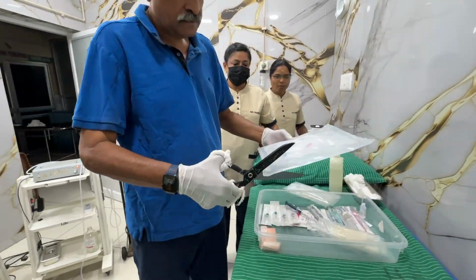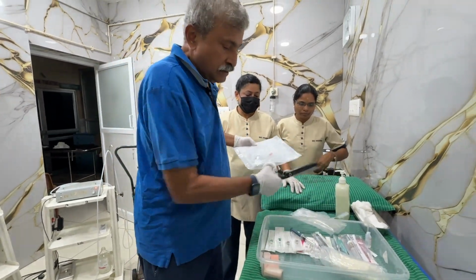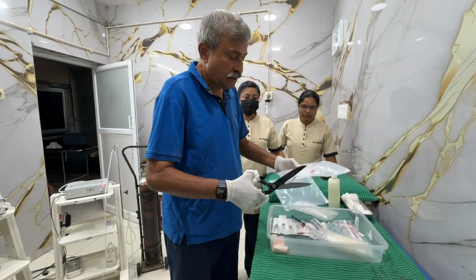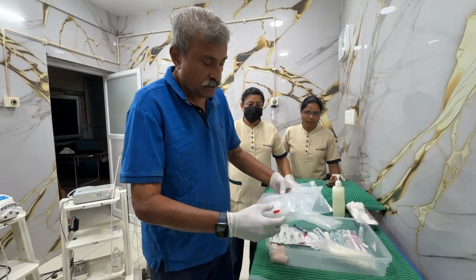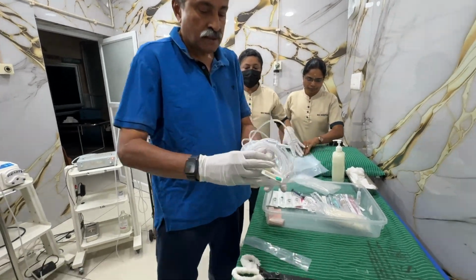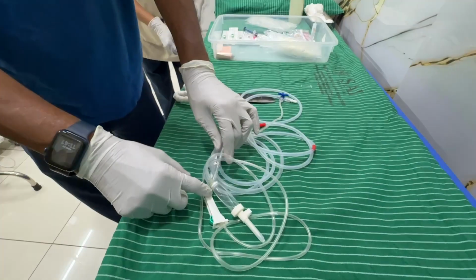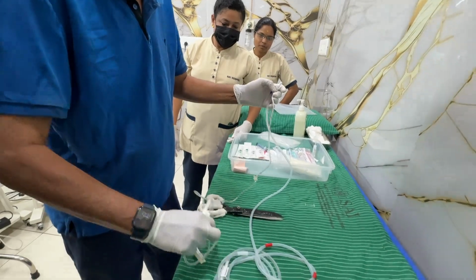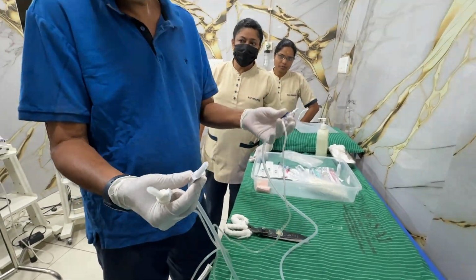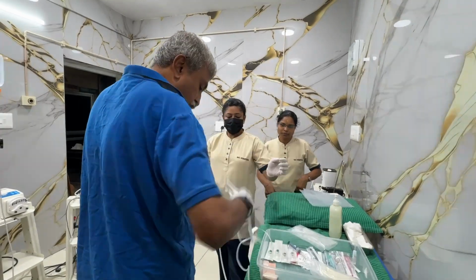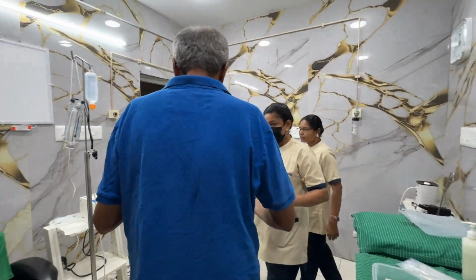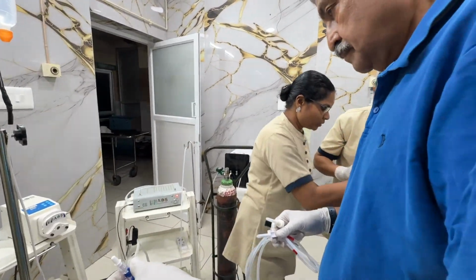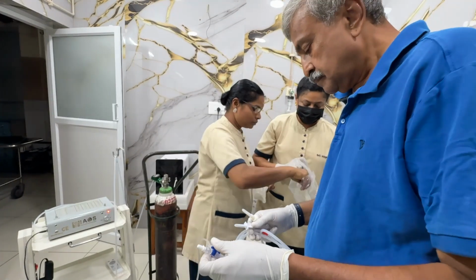This is the Gen X EBOO set, which comes pre-sterile. These tubings are made out of medical grade silicone with no junctions. There are only 2 connectors, one that goes into the patient's body and one that goes into the bottle. In between, the patient's connector is also attached by a 3-way to heparin, so that heparin mixed with patient's blood is drawn into the EBOO flask.